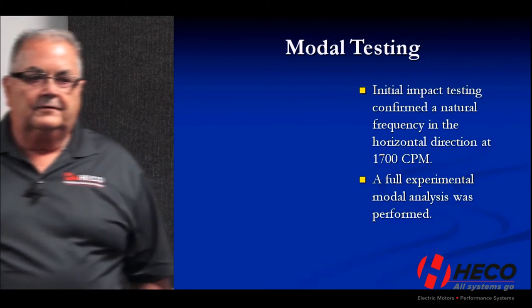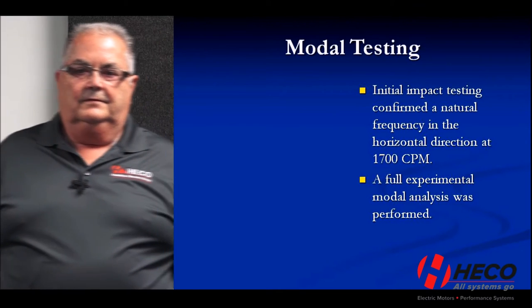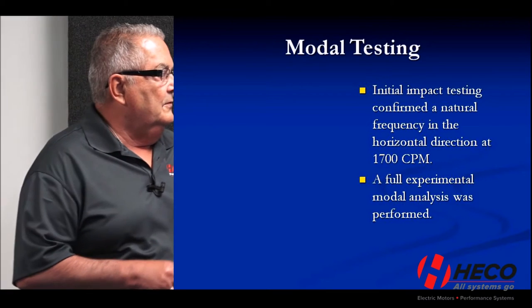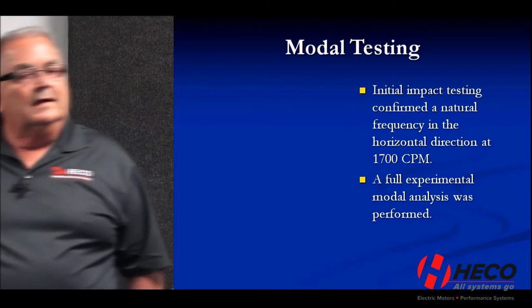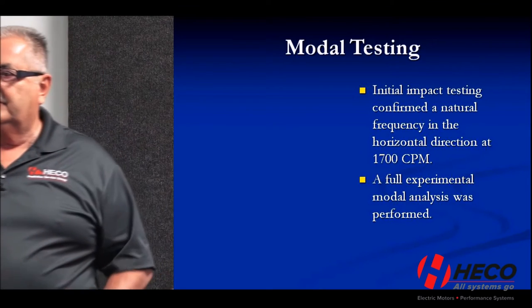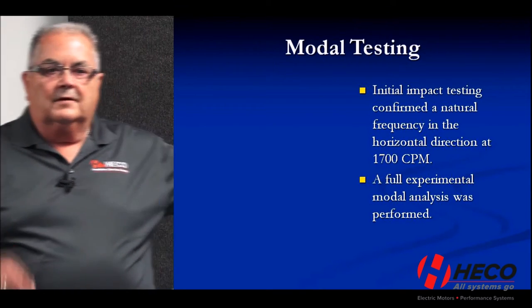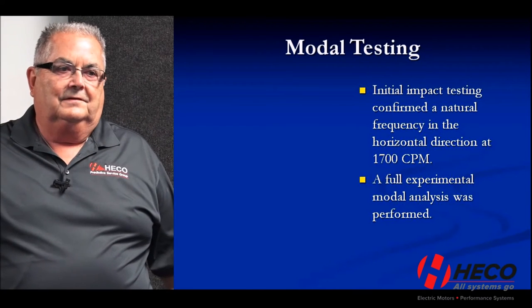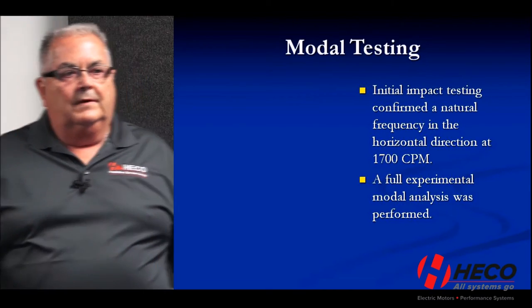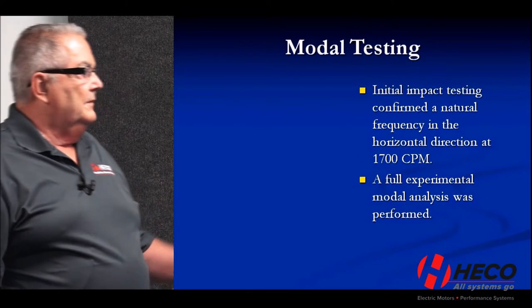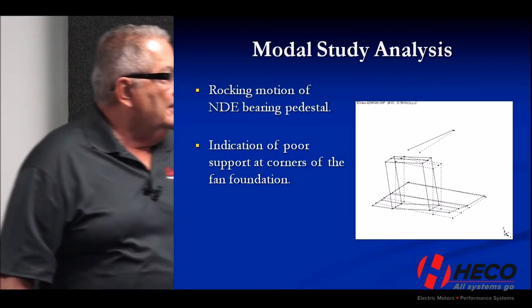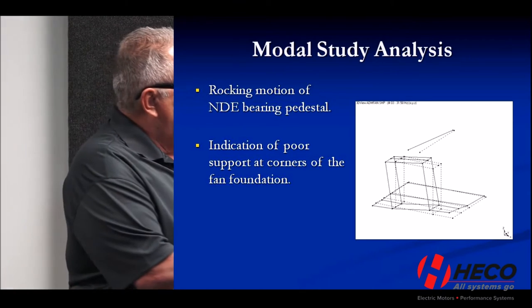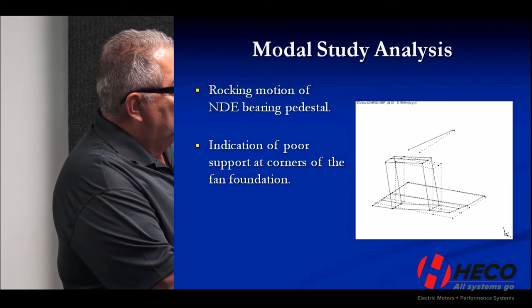Knowing we have a natural frequency, and given that this is a large fan — not a trivial fix — we said we really ought to do an experimental modal analysis to see how stiff this fan structure is. Modal analysis tells you how much force it takes to generate that level of vibration. If there's a resonance, it could take very little force to cause that much vibration. So we went in and did a full experimental modal analysis.